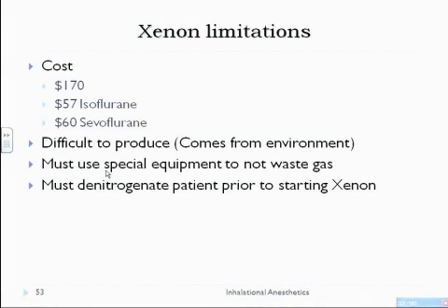The bad thing also is that it's difficult to use, in the sense that you need special equipment to not waste any gas. You have to have very tight closed systems, like I showed you in the previous machine. And if you want the agent to work properly, you've got to denitrogenate the patient completely before you start the agent. So that's a limitation.